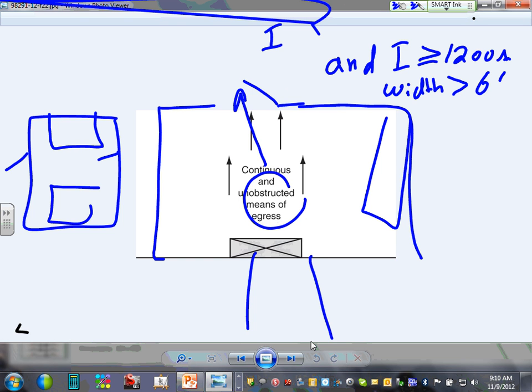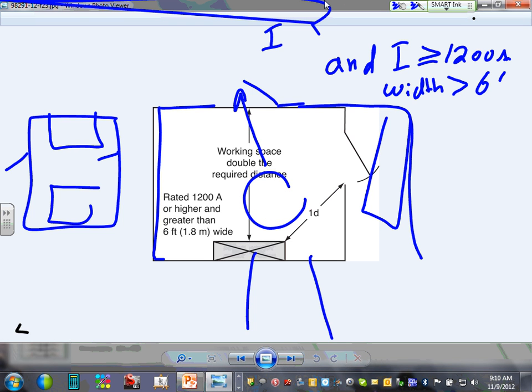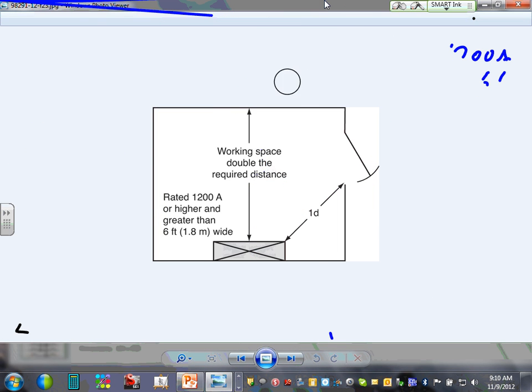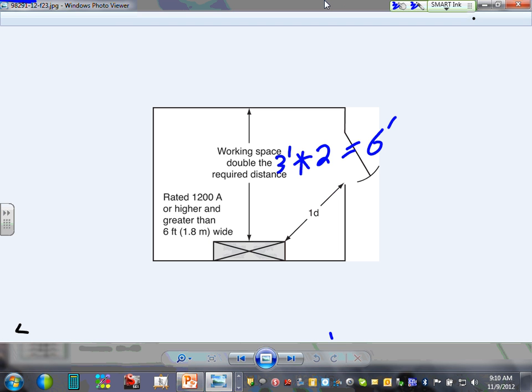So that's unobstructed. The second option, guys, is to avoid putting 2 doors. And I'm sure you guys sitting and said, who cares about 2 doors, Chad? Let me tell you about who cares about 2 doors. The second thing is to double the distance. If this is supposed to be greater than 6 feet, if this is supposed to be 3 feet, you double it, multiply it by 2, that will make you 6 feet. Then you can only have 1 entrance. Can I have thumbs up, Chad? Doubling it. But this distance here, from here to here, cannot be less than 3 feet.